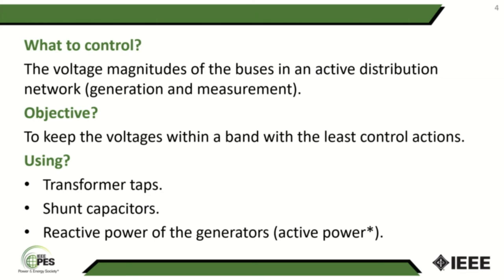So, our interest here is to propose an algorithm to control the voltage magnitudes of the buses in an active distribution network, with medium voltage distributed generation and measurement infrastructure. We intend on using a centralized scheme to coordinate the control actions of all the assets of the grid. However, this controller will also be able to cope with voltage measurement losses. The objective is to secure the monitored voltages within a band with the least control actions as possible. The assets I mentioned previously are the taps of transformers, shunt capacitors, and the reactive power setpoints of the generators. The active power is also considered a control variable, but with a very high cost to its curtailment.